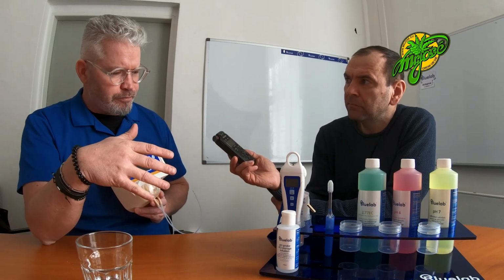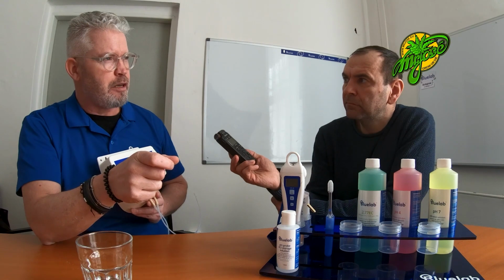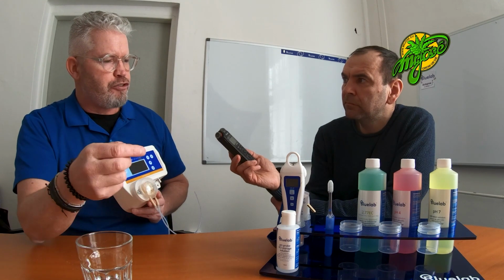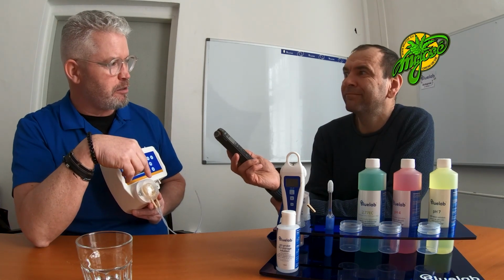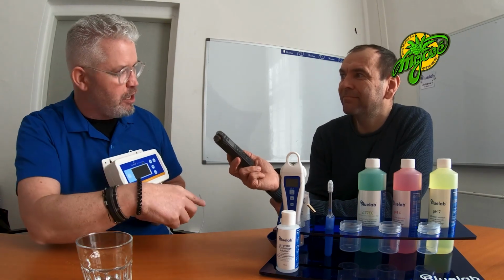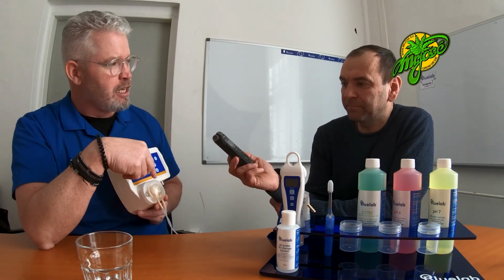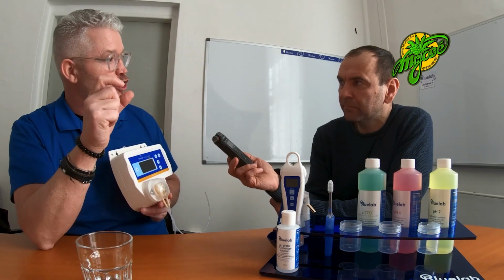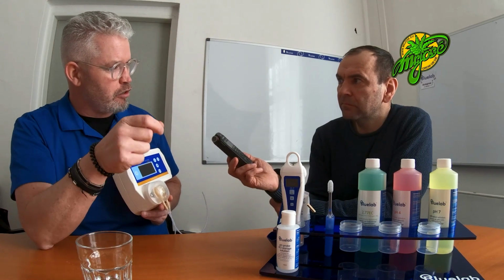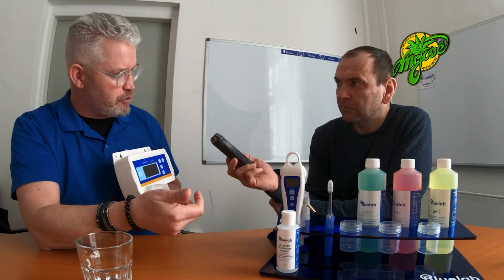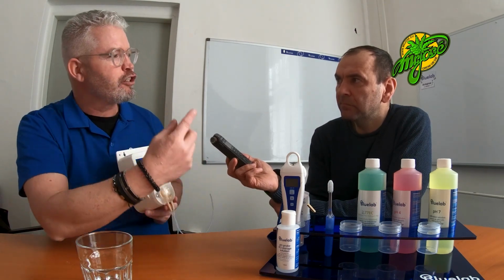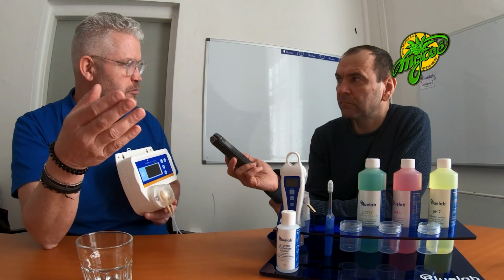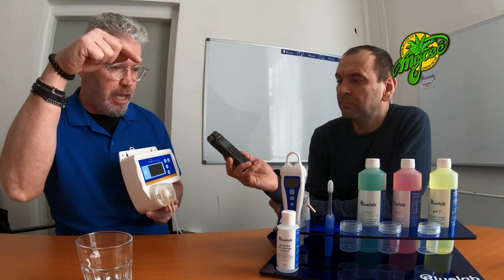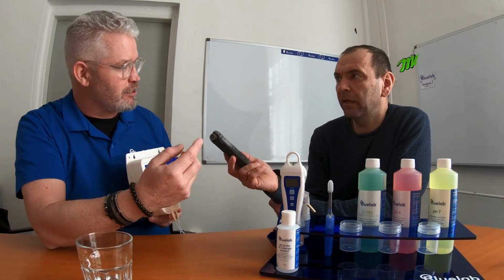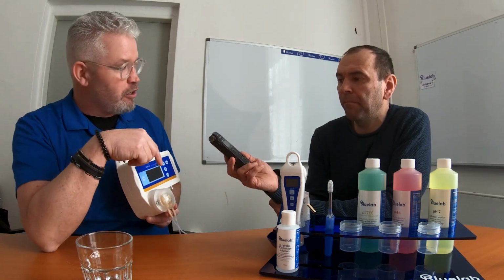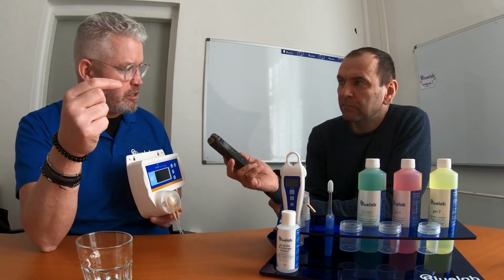The dosing time is important because you don't want to dose all the way to the set point, since sometimes you'll overshoot below it, and you don't want that. So we have a security feature - you set the amount of seconds so you're not overshooting. Sometimes when the water is soft, the pH drops faster than when the water is harder, which is why you have this dosing time.